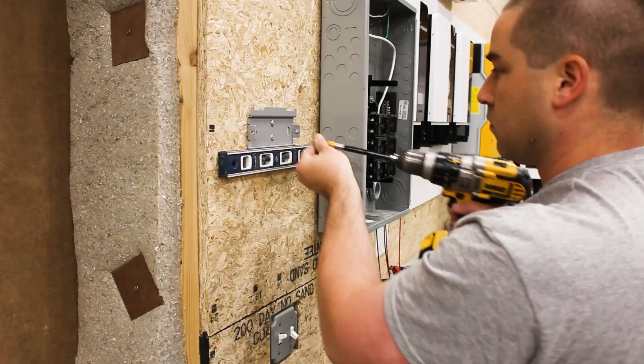So I have 3 circuit breakers for the 3 inverters, each one running on its own. Out of the AC combiner box, right down here on the very bottom, I have 1 circuit breaker that is a 30 amp circuit breaker. It runs to the auto transformer. This is a 5,000 VA auto transformer from SolarEdge, and all of this stuff you can buy from Signature Solar. Now the auto transformer is what gives me my neutral, and that is fed into the neutral bar of this AC load center. Out from that, I then have 2 more circuit breakers to 2 different loads.